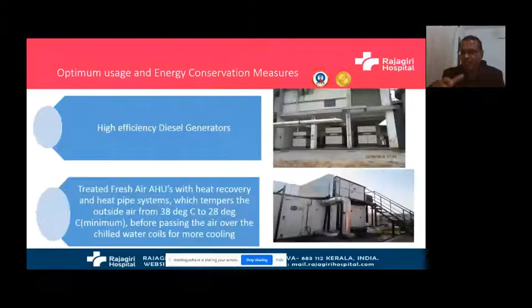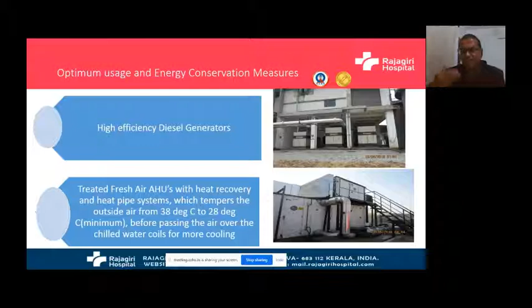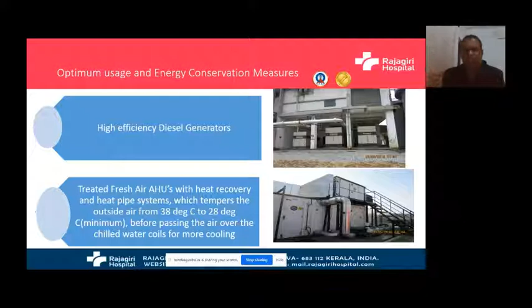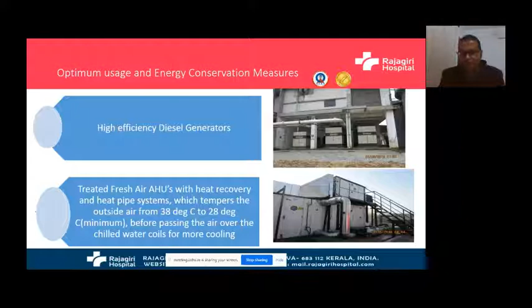Now we have a lot of air being exhausted into the atmosphere because of ventilation. That air is cold, chilled air. We can actually use heat recovery systems, plate type heat exchangers in the treated fresh air AHUs, thereby capturing some of the cooling that is being sent into the atmosphere because of the process required.